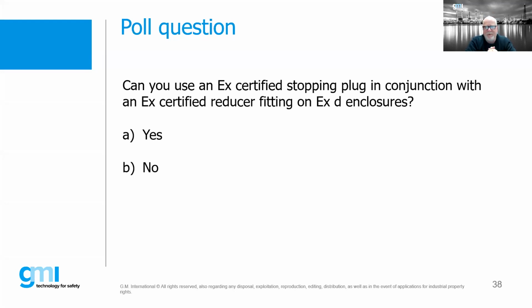So what can we use? We can use a certified reducer with a gland - meaning if we have an entry that's M25 and a gland that's M20, we want to reduce it down so we can use that gland. That's fine, we can use an M25 to M20 reducer with a cable gland in it. However, if we come back to that same entry with an M25 hole and an M20 plug, and we want to use that M25 to M20 reducer with the plug, that's not allowed for EXD equipment.